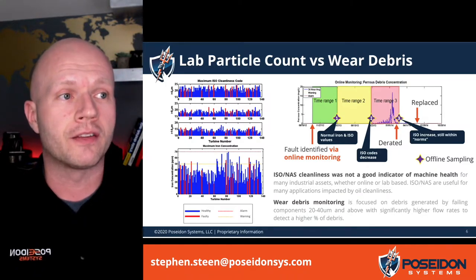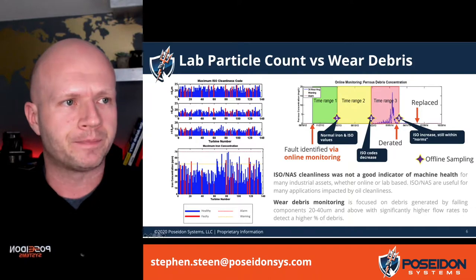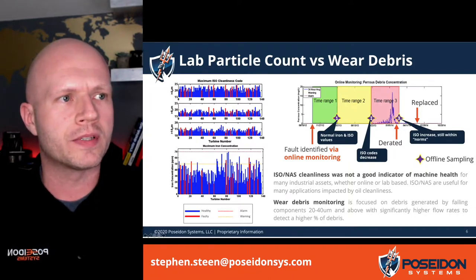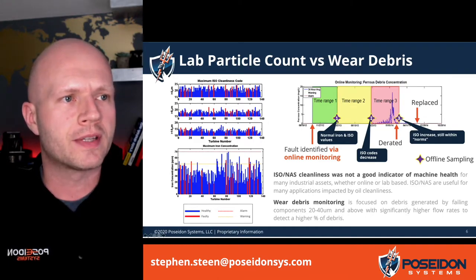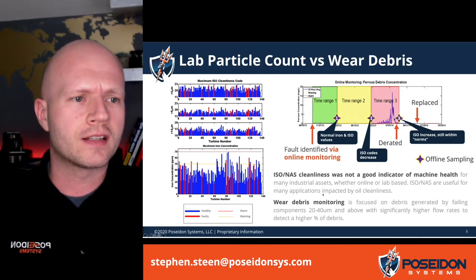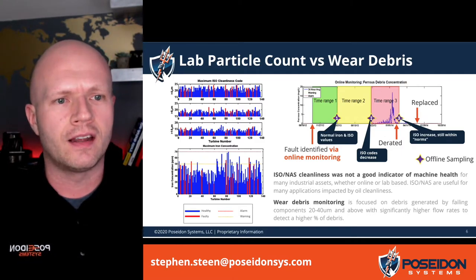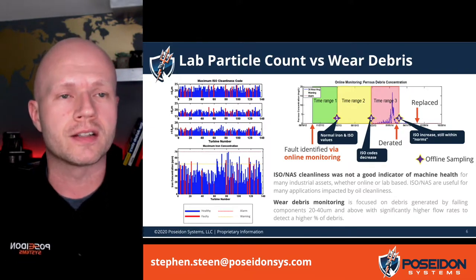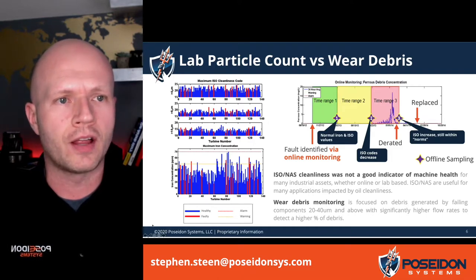Compare that to an example from that same fleet on the right hand side using a wear debris sensor. We were able to catch that fault relatively early and trend it over time to determine when it was getting really bad, as you can see from that spike. From this, compared to the lab samples, you can see that those all came back within spec. A lot of that has to do with the fact that the chances of pulling large wear debris into an oil sample sent in once, twice, or maybe six to twelve times a year is very small — whereas online oil sensors are able to see them happening at all times, getting quite a high flow before they get trapped in the filter.